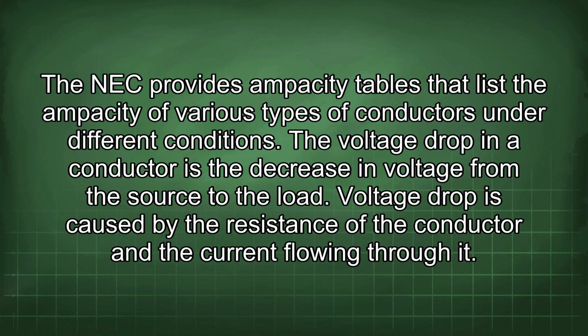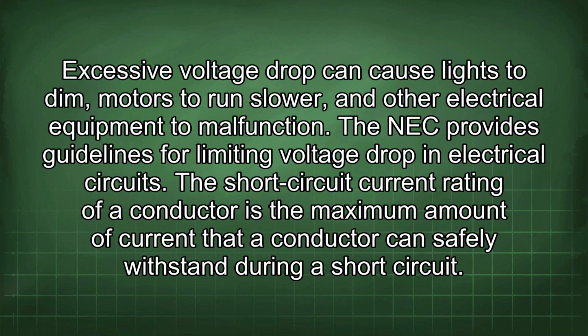The voltage drop in a conductor is the decrease in voltage from the source to the load. Voltage drop is caused by the resistance of the conductor and the current flowing through it. Excessive voltage drop can cause lights to dim, motors to run slower, and other electrical equipment to malfunction. The NEC provides guidelines for limiting voltage drop in electrical circuits.